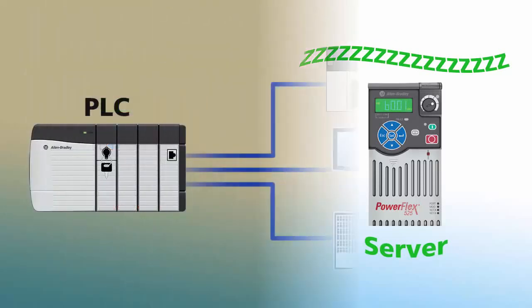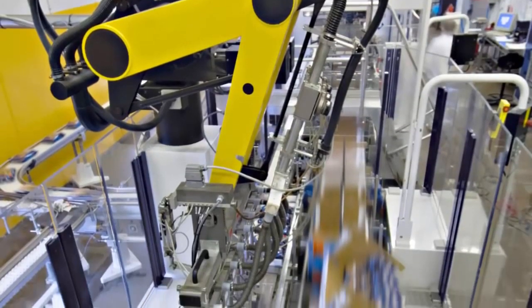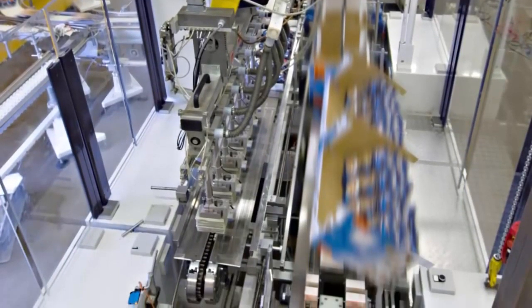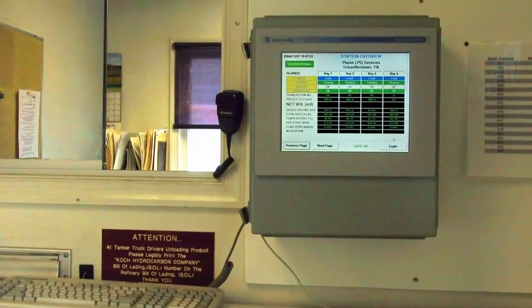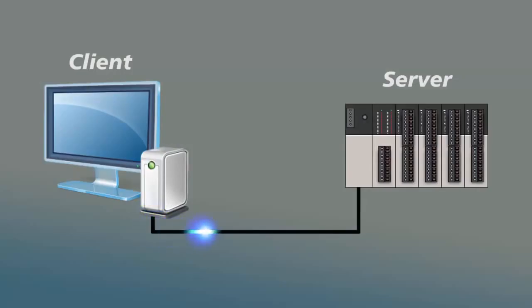It's possible for a PLC to act as a client, a server, as well as an I/O messaging master simultaneously on the same network, communicating with various server devices and clients while controlling remote I/O devices as applications demand. I/O message communications are given higher priority by the processor, while client-server data messaging are given lower priority. I/O messages are designed to run at regular time intervals, meaning the communication speeds are consistent, whereas regular data messaging speeds are dependent on the availability of unused processing power.